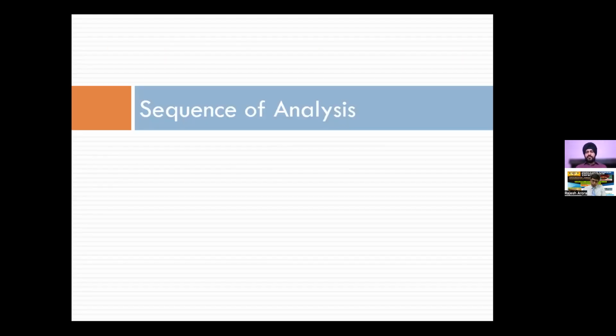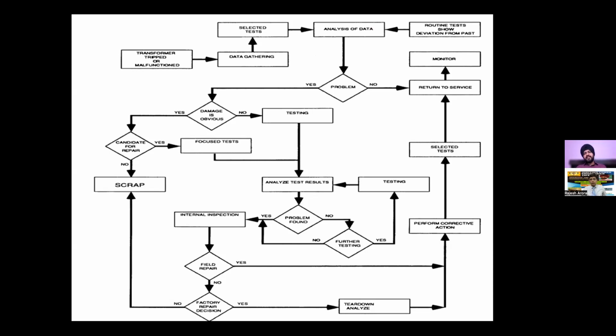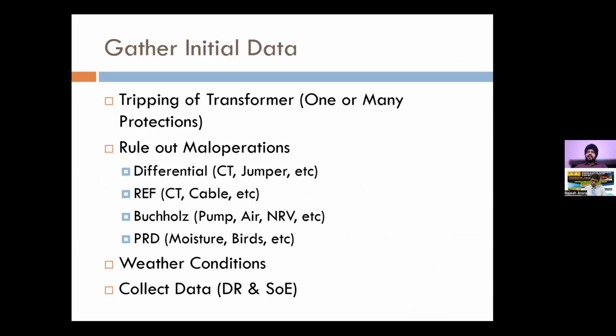So how to analyze? What should be the sequence of analysis once something like this has happened? This is a flow chart which describes the sequence of what should be done, right from when it starts to how it should end. But let's go through it one by one. First of all, whenever there is any tripping, you should gather all the data. How many protections have operated? Mostly, with transformers, we have electrical protections and mechanical body protections, like Buchholz and PRD, then differential and REF. Whenever the transformer trips, you should first check how many protections have actually operated. Did all those protections operate, or did only one operate?